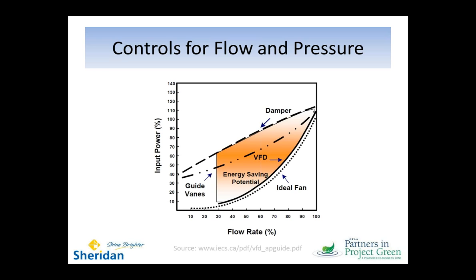And this is really highlighting that the outlet damper, which I was talking about in the top right of the previous slide, doesn't have very effective control for us. If I'm at 100%, starting at the right-hand side, I've got 100% flow, and I decide I want to dial back that flow to about 50%. If you follow the curve down for flow rate from 100% to 50%, what you'll see is that at 50%, your energy consumption of that motor, your input power, is still up around 70% for an outlet damper.